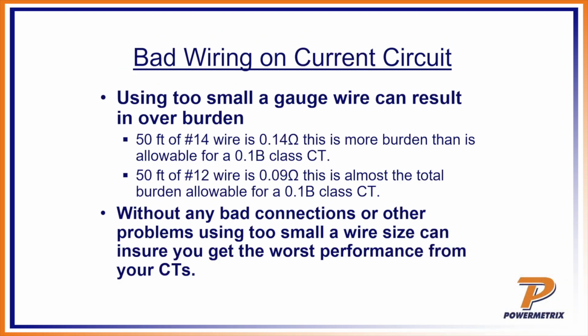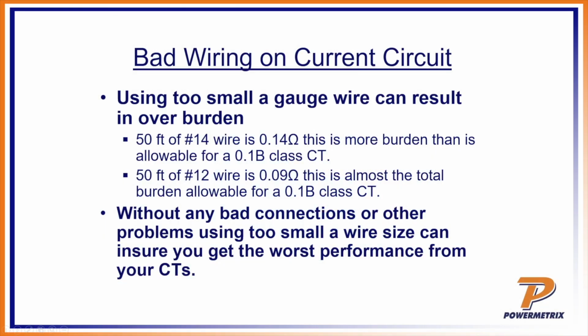So now what about bad wiring using too small a gauge of wire? That's why we don't run 14 anymore. We run 12 and 10. It's because 50 foot of number 14 wire is 0.14 ohms of resistance alone, just the wire itself. And for a 0.1 class CT, you're already over it. And 50 foot of number 12 has you right there at it. So that's why we've seen people go 14, then 12, and now you're seeing so much 10 out there, because it gives me more leeway. I'm not already at the limitation of the CT with just the wire alone, possibly overburdening it. So you can see there at the bottom, without any bad connections or other problems, using too small a wire size can ensure you get the worst performance from your CTs.